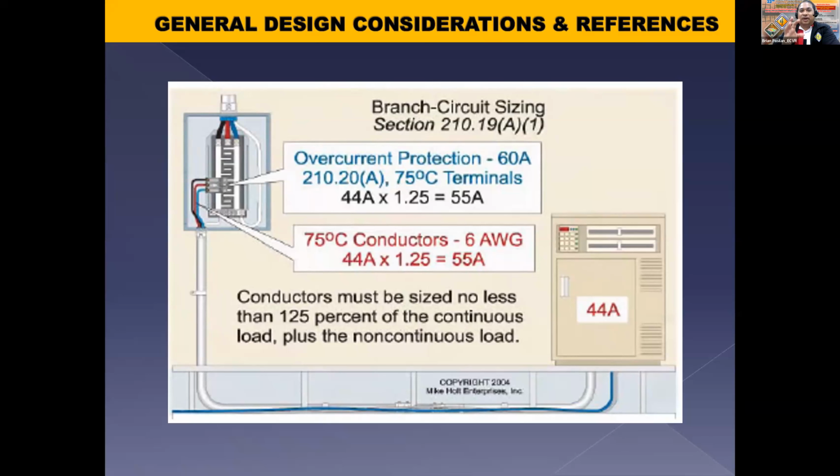But if it's a part of a multiple outlet, hindi natin alam yung ibang outlets, no, mag-add yan ng current sa conductors mo, hindi na predetermined yung current natin. So may chances na makakacause na yan ng overloading ng circuit natin. So kaya nga hindi allowed sa mga multiple outlets ang next higher standard rating ng circuit breaker natin. Yun yung wisdom niyan. Bakit ina-allow siya?